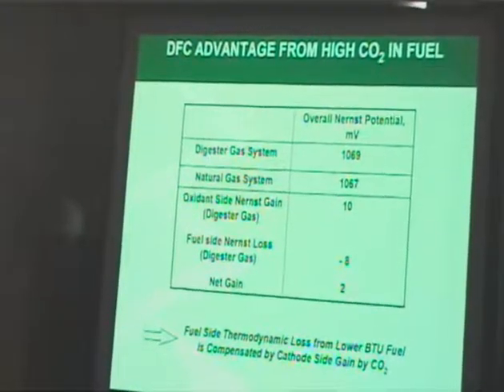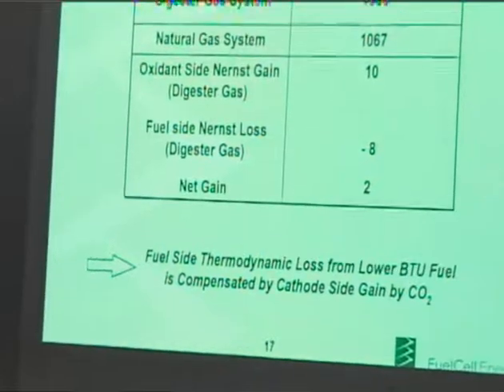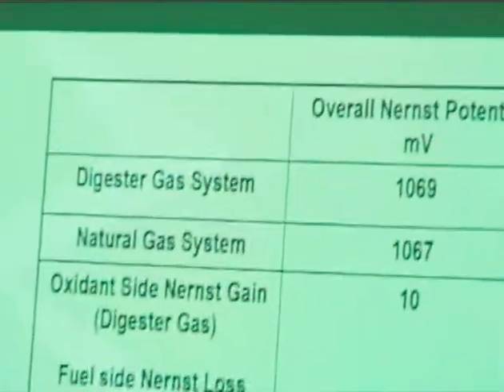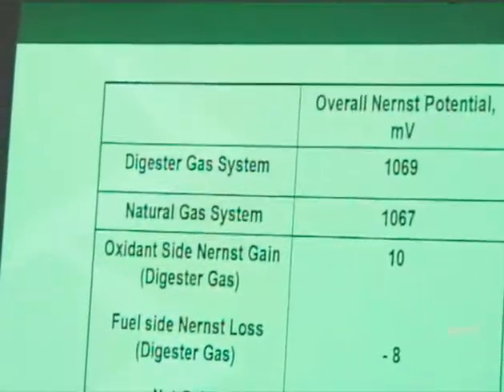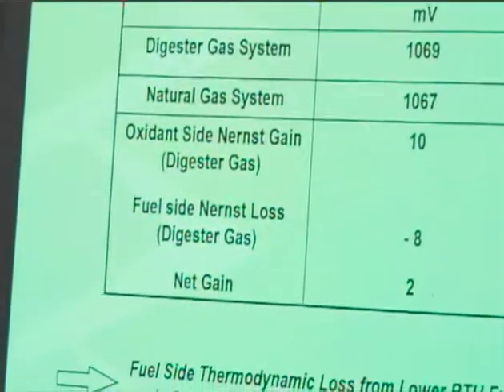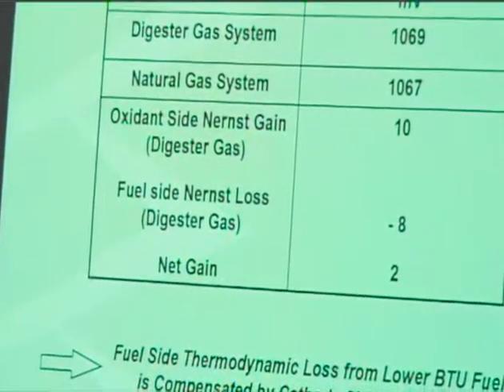You gain approximately 2 millivolts. As I said, because of the CO2, the polarization and Nernst losses are lower on the cathode side, and you are benefited by approximately 2 millivolts. That isn't a big thing, but it directly relates to how much output kilowatt you are getting out of the power plant.